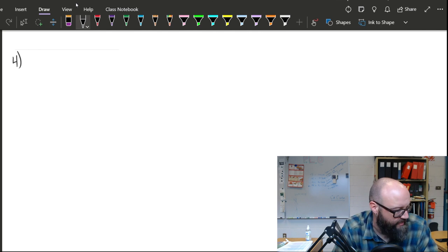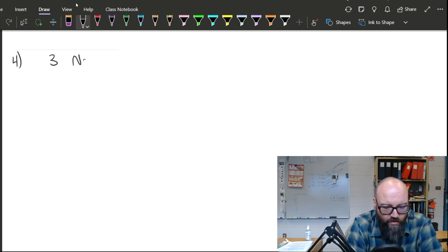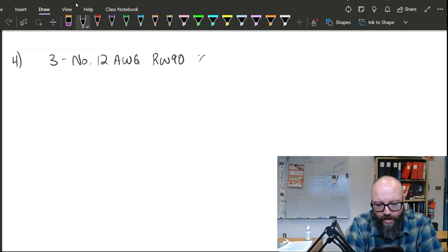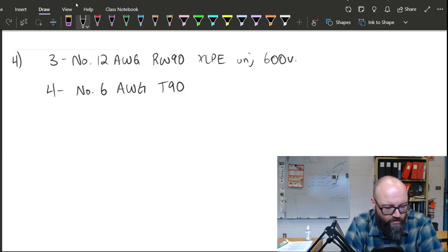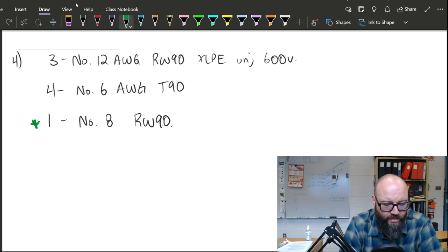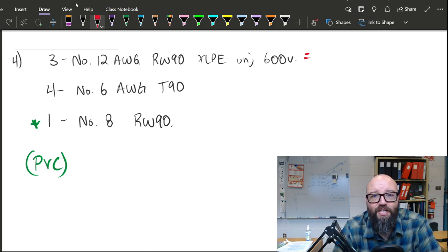In this example, let's say we have 3 number 12 RW90 XLPE unjacketed 600 volt. We're going to say that we have 4 number 6 T90 conductors, and we're going to say we have 1 number 8 RW90. This is going to be our bonding conductor because we're going to say that everything is going to be in a PVC raceway.